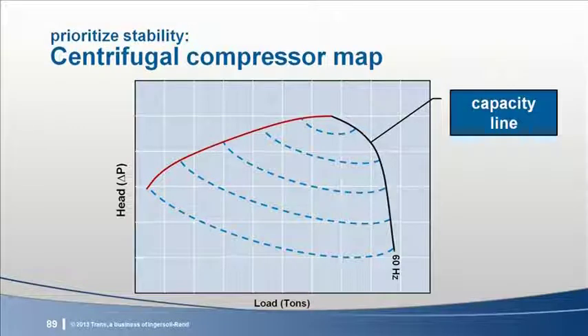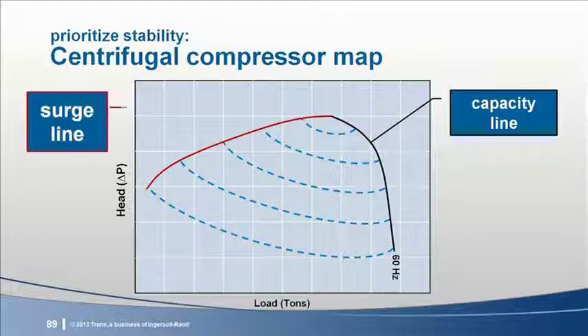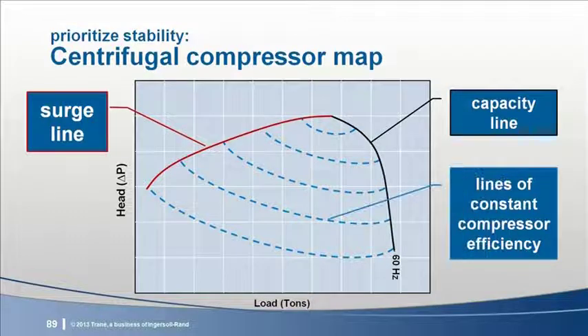This is the highest capacity the compressor can produce at a given speed and inlet guide vane position. On the left is the red surge line. This is effectively the lowest capacity the chiller can produce. Attempting to operate to the left or above this line will result in unstable, surging operation. The dotted blue lines represent lines of equal efficiency, sometimes called efficiency islands. The top curve represents the best compressor efficiency with decreasing efficiency at lower islands.